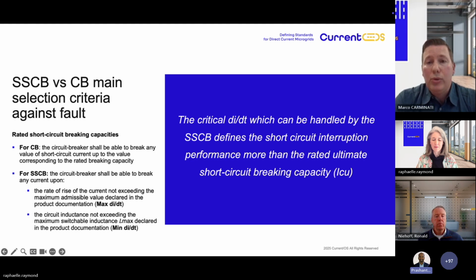Instead, if we would like to select a solid-state circuit breaker, in this case, the circuit breaker shall be able to break any current upon the rate of rise of the current not exceeding the maximum admissible value declared in the product documentation. Basically, it is a maximum di/dt of our fault current. So no matter about the peak value of the current, the maximum value, the steady state value, but here it is a matter of the derivative of the current, and also the circuit inductance not exceeding the maximum switchable inductance declared in the product catalog, basically.